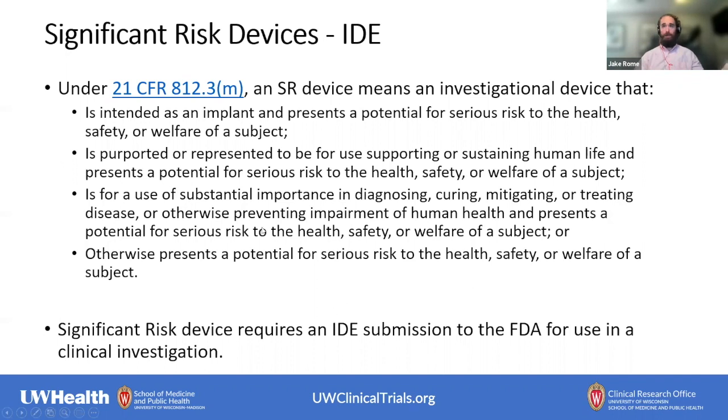If your device meets the definition of significant risk, then it would require a submission of an IDE to the FDA before you could use it in your clinical investigation. And one important thing to note about device evaluations and the definition of a significant risk device is that the requirements don't only apply to the risks associated with the device specifically, it applies to the risks associated with the study as a whole. So as an example, you may be using a device that does some sort of stimulation of a subject.